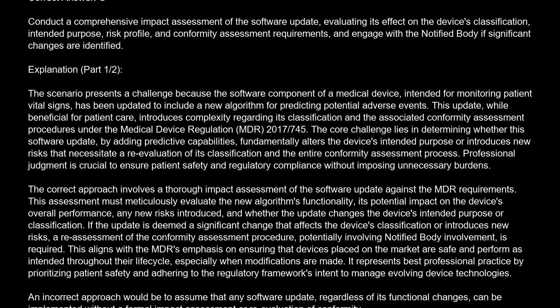2017/745. The core challenge lies in determining whether this software update, by adding predictive capabilities, fundamentally alters the device's intended purpose or introduces new risks that necessitate a reevaluation of its classification and the entire conformity assessment process. Professional judgment is crucial to ensure patient safety and regulatory compliance without imposing unnecessary burdens. The correct approach involves a thorough impact assessment of the software update against the MDR requirements. This assessment must meticulously evaluate the new algorithm's functionality, its potential impact on the device's overall performance, any new risks introduced, and whether the update changes the device's intended purpose or classification.